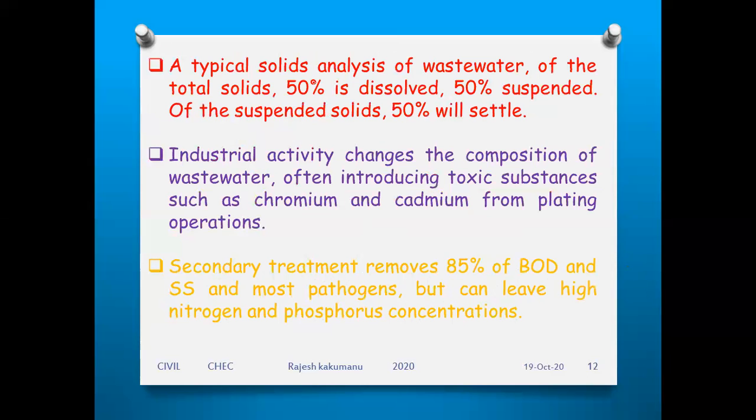A typical solids analysis of wastewater. When you read the analysis of the wastewater, of the total solids, 50% is dissolved and 50% is suspended. Of the suspended solids, 50% will be settleable. Okay, so 50% dissolved, 50% suspended, 50% will settle.